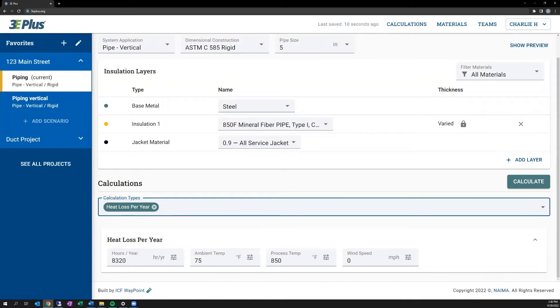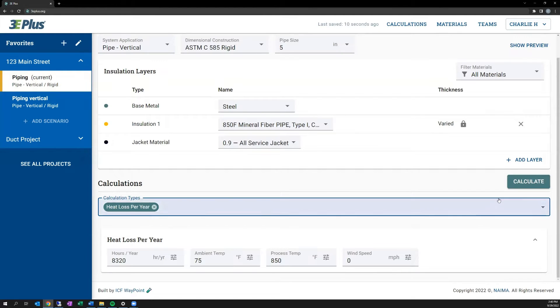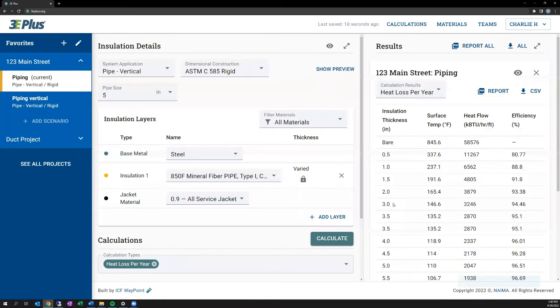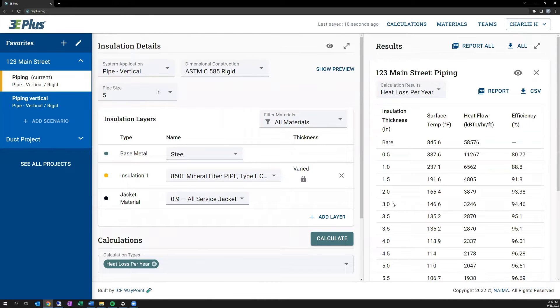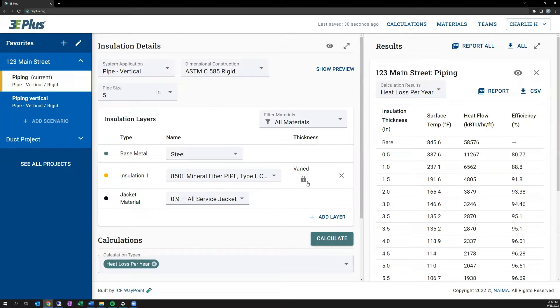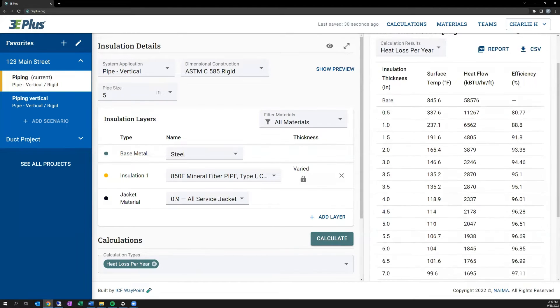So in this case, we'll enter 8,320 hours in a year that it would be operating, and we'll hit the Calculate button off to the right. It will display the annualized results for the same setup that we had under the heat loss calculation. So this will display the surface temperature, the heat flow. But now they're annualized, and the efficiency is included over a range of insulation thicknesses, because again, we set the thickness to varied.